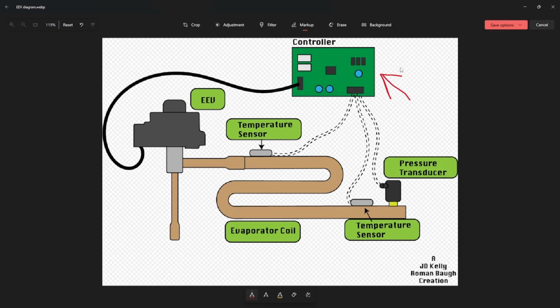My brand that I'm most familiar with is Rheem and Trane. So I'm going to use Trane as the example here because Trane has EEVs on almost all of their TAM units. It's extremely common to run across EEVs on TAM units. So in a Trane, this board would be called our EVC, Evaporator or Expansion Valve Control. Our EVC has a number of different components connected to it. We have the cable here, which goes to our stepper motor or our EEV.